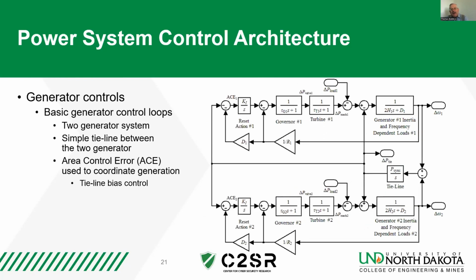Then we get to the level of providing area control error, where now these are the inputs from not only proper operation of our generators to maintain frequency, but also maintain our contractual arrangements of how much power should be flowing across tie lines and making sure that our balancing authority is meeting its contractual arrangements through the area control error, and that tied with our maintaining of frequencies for proper generator output to run percentage-wise, to run economically. All those are put into balance with a control system this way.